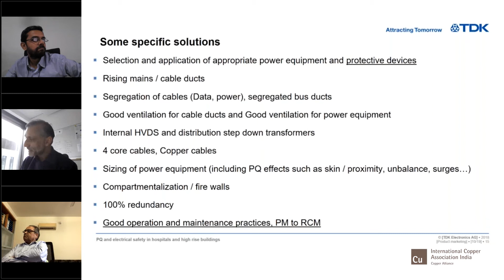Definitely 100% redundancy. Why redundancy here? Let's say you're on the 75th floor, the mains burns out, the lifts don't operate, then you cannot evacuate anyway. So for hospitals and high-rise buildings, in the electrical system there must be an A system and a B system. And the B system must be totally independent from the A electrical system. There must be a primary electrical and a secondary electrical system, and they must be totally isolated galvanically and physically, so that the failure of one electrical system does not affect the performance of the second electrical system, which may not have the full power, but can provide the emergency services.